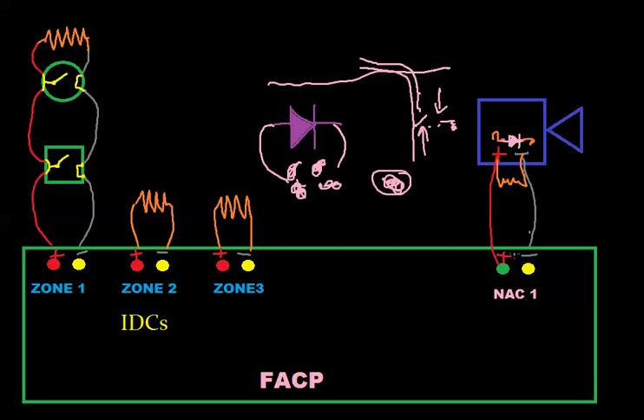We'd have a negative voltage in a standby state. When this panel goes into alarm, once one of these shorts, we're going to short this pull station. Now the panel detects an alarm. This little red alarm light would come on. And now the polarity is going to reverse. The leg that says positive is actually going to be positive, the leg that says negative is actually going to be negative. Now since the current's flowing this way, this diode will pass through and pass the current into this horn strobe, and now the horn strobe will come on.